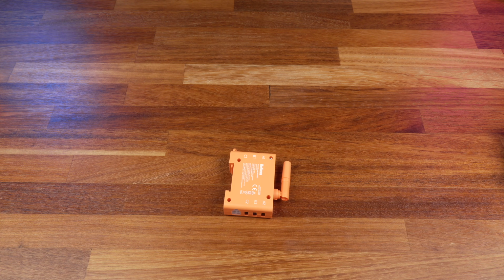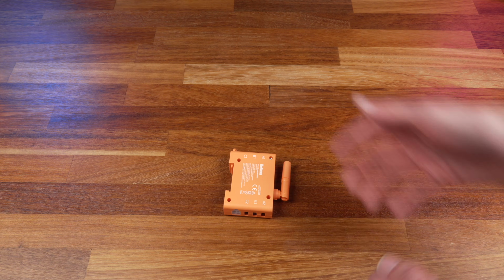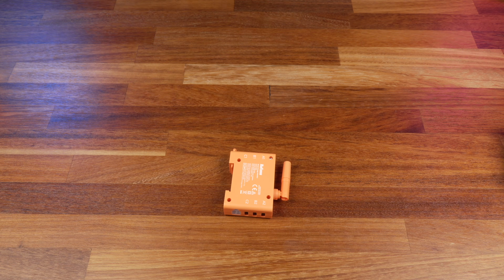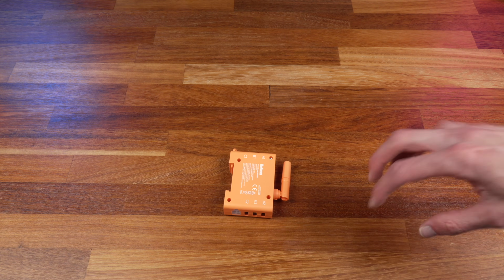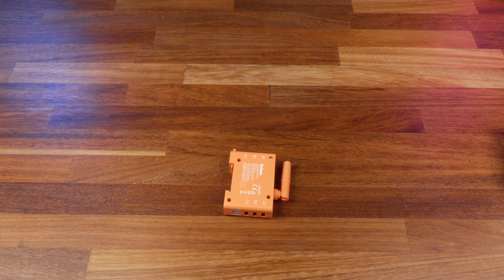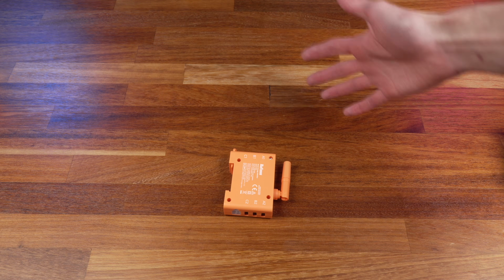Now for me on a single phase setup, that's no big deal, since all these will be on the same phase, so I can just connect my CTs without much worrying. But if you're monitoring a setup with multiple phases, you need to bear this in mind. You couldn't connect this to, say, a 3-phase supply and then decide you want to monitor 3 circuits on L1, 3 circuits on L2, and not monitor any circuits on L3. Your CT inputs are fixed to 2 CTs per phase.